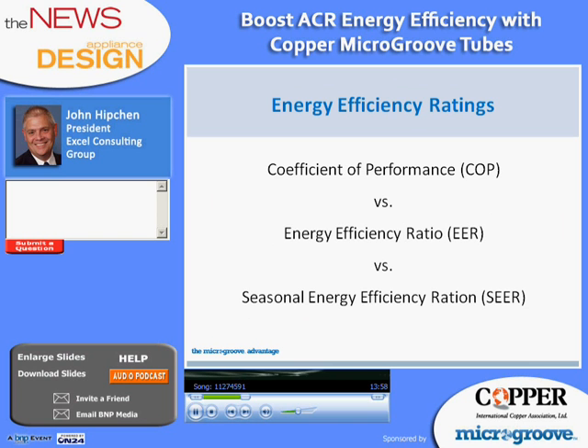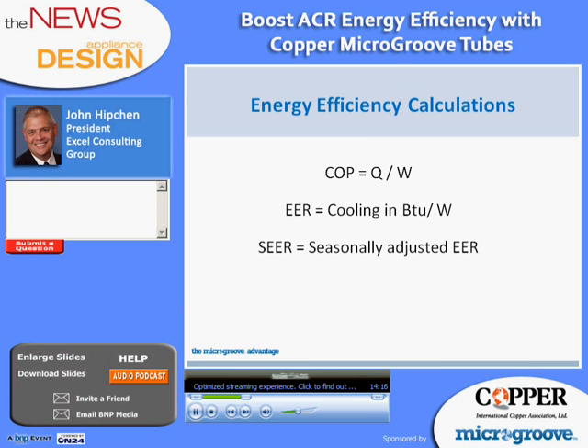Energy efficiency is typically rated one of three ways: the coefficient of performance, or the COP, the energy efficiency ratio, or EER, and the seasonally adjusted energy efficiency ratio, or SEER. When we look at how these ratings are calculated, we see that the COP does not have units because both the cooling load, Q, and the input power, W, are measured in watts, and watts cancel each other out. So for the purposes of this webinar, we'll look at EER ratings. Energy efficiency ratio is calculated by dividing the output cooling, measured in BTUs per hour, by the input electrical power in watts. So the units for energy efficiency ratio are BTUs per watt hour.